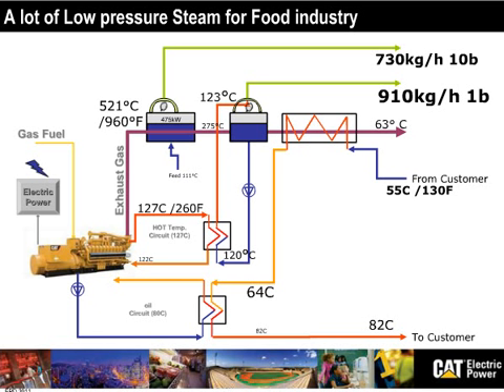And the beauty of this is if you would use a normal jacket water temperature genset around 90 degrees, you would be able to produce only 1 ton per hour of steam per megawatt electrical. And if you use that system, you can produce 60% more, 1.6 ton of steam per hour. So that's a very big difference. Keep that in mind. We can produce steam. I mean, it's a well-known fact that gensets cannot produce a lot of steam compared to other equipment. Yes, that's still correct. But if you need steam, we can have some. Let's look at your temperatures and let's look at your pressures. Reinhardt is correct.